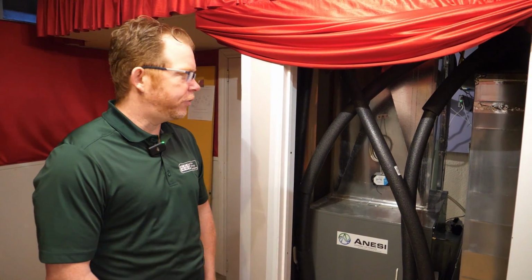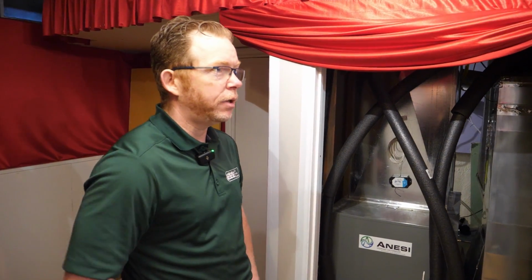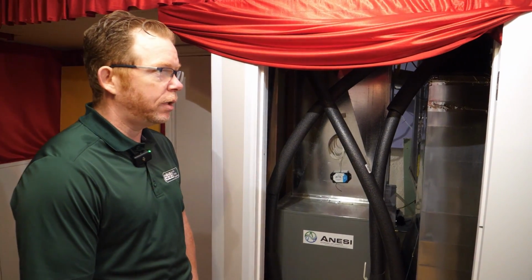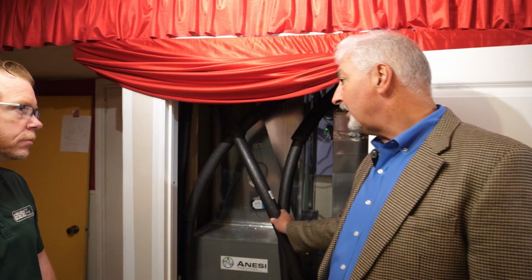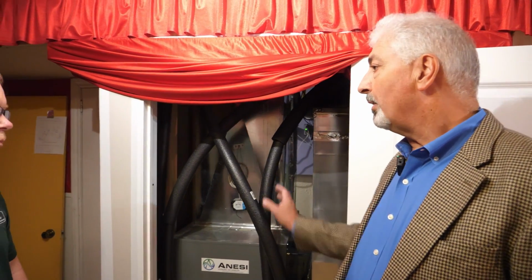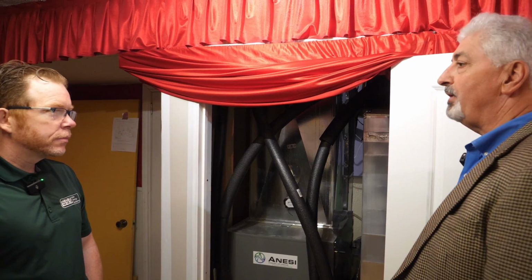It's good to plan, and it sounds like you guys have with a circulator that can overcome anything that they might pipe it in, whether it's PEX or copper or whatever the case may be. Absolutely. Let me remark too, real quickly, this could be 1-inch copper. If it's PEX, we want it to be oxygen barrier PEX. It needs to be oxygen barrier so that we preserve the integrity of the hydronic.